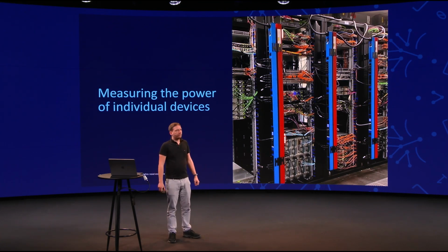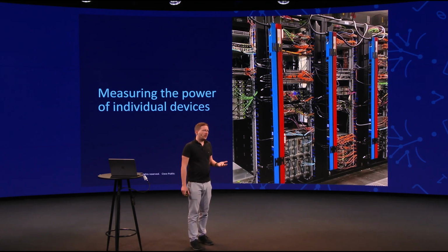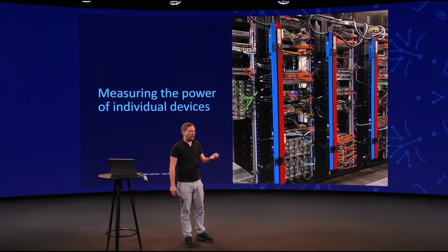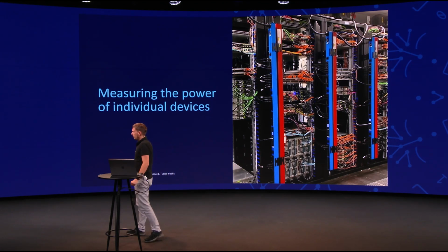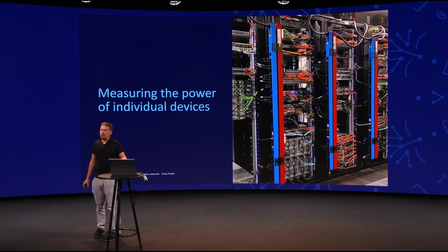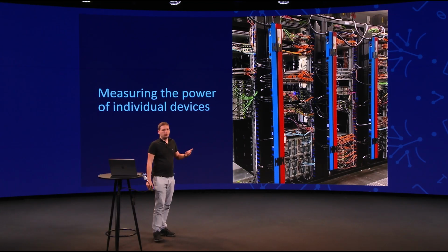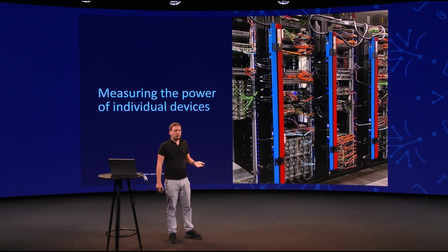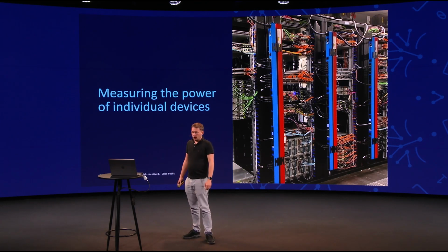And some devices, especially the ones that have modular power supplies, also have AC sensors, so what goes into the device, right? And why that matters is, of course, and I think Bertrand mentioned it in the beginning, it has to do with the 80+ program, for example: power supplies do have conversion losses, of course, because they are converting power, and what is lost in terms of power is wasted as heat.